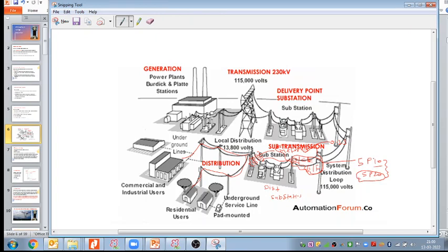If there is any special requirement of the client, if they are asking for the PX core in their tender specification, in that case we can select it, that is not wrong. But 5P is what we should take here. We can take PX only if there is a special requirement provided by the client.